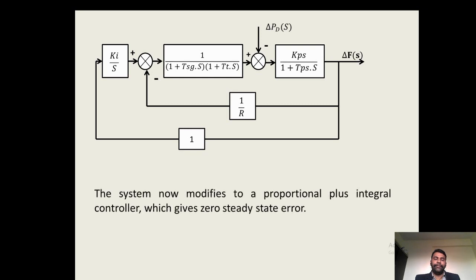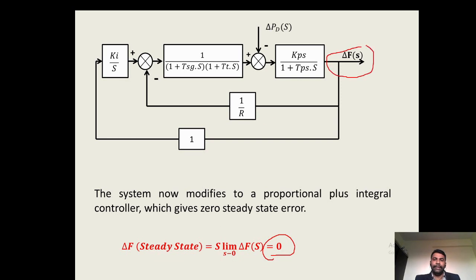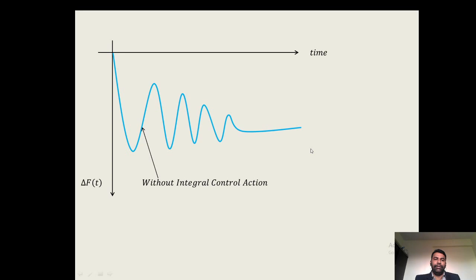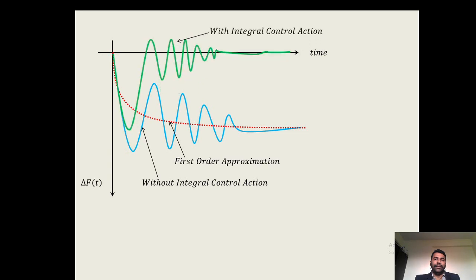When we find out the steady state change in frequency, we will see that the steady state change in frequency for this particular system becomes 0. So, we can say that with the help of the integral controller, the change in frequency at this point becomes 0. We will now see the graph of frequency versus time. For a positive change in the load, the change in frequency is given by this curve. This is without integral control action — this is the first-order approximation. This is the frequency response for integral control action.